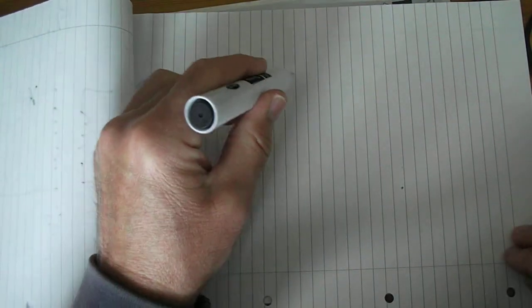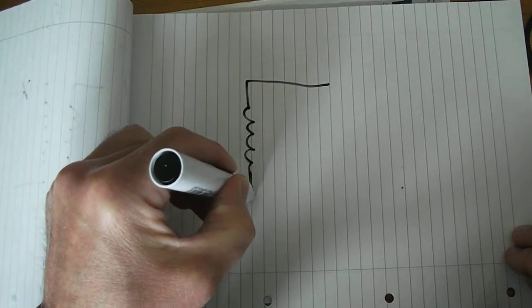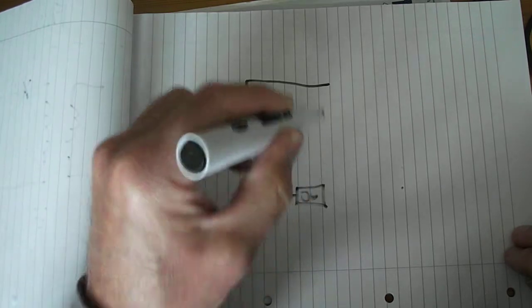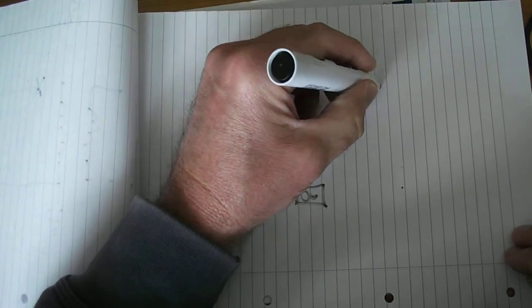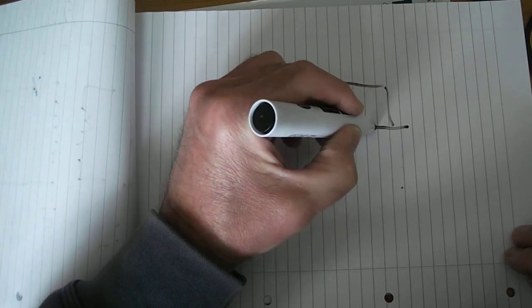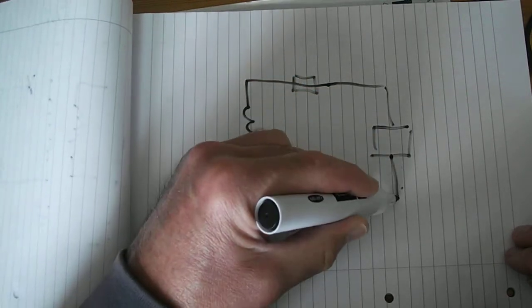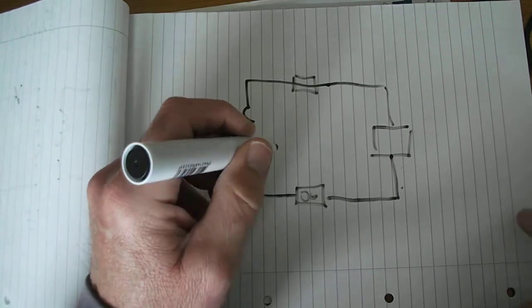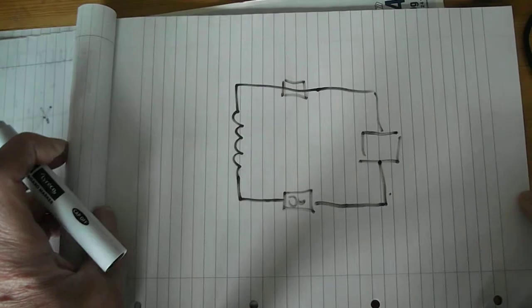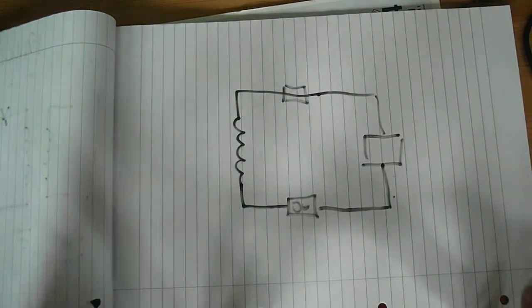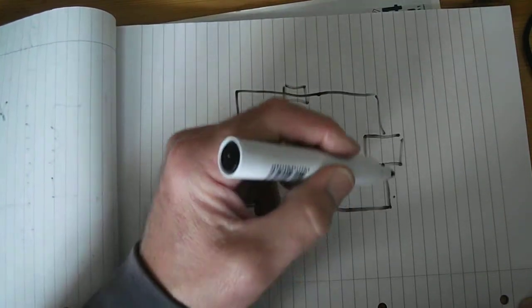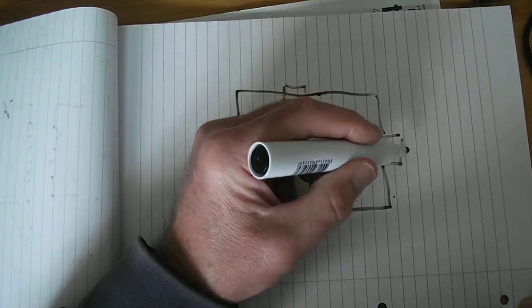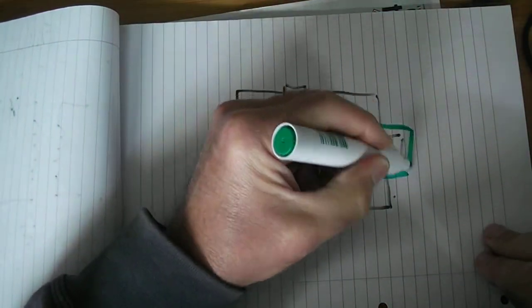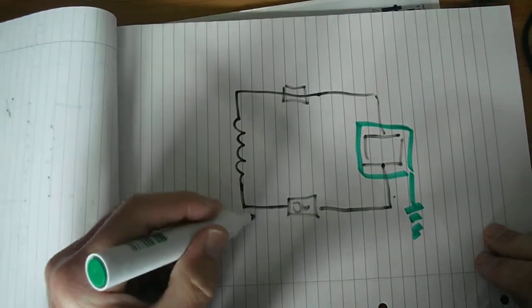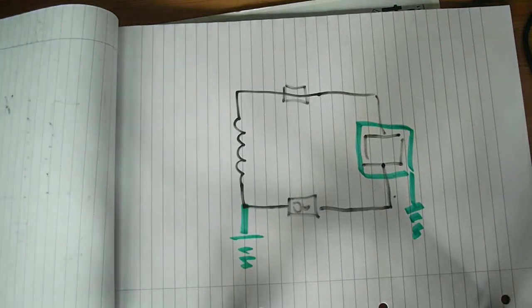You remember from our video on earthing, there is our link, there is our fuse, and there is our appliance, and there is our circuit there. Now in a TT situation, which is terra, where we need electrodes, you remember we have an electrode at the consumer end. So here is our electrode down here, stuck in the ground, and we have an electrode, of course, back at the substation or the transformer on the pole.